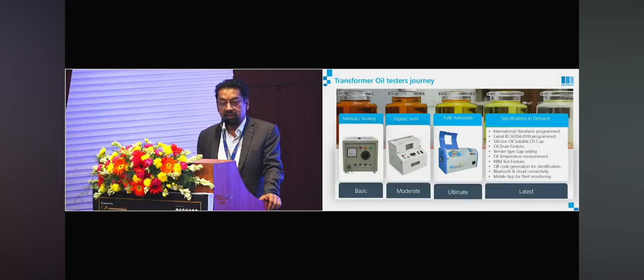In earlier days, they were only measuring the dielectric strength of the oil. Now they want to measure the temperature along with that: at what temperature, what is the dielectric strength? So oil temperature measurement has become essential. They want real breakdown monitoring also, with sensing of the breakdown on the primary side as well as the secondary side.